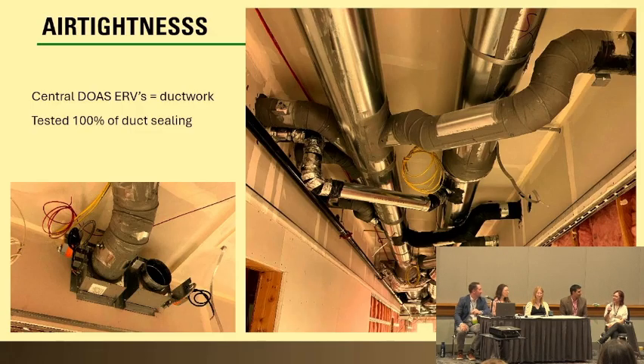I'll just add that on the project in Seattle, the duct design was very repetitive, so we were able to mock up one piece, figure out our QC measures, test that piece, and repeat it over and over. This design didn't have that repetitive nature, so it made sense to go ahead and test all of it, even though it was a big task.